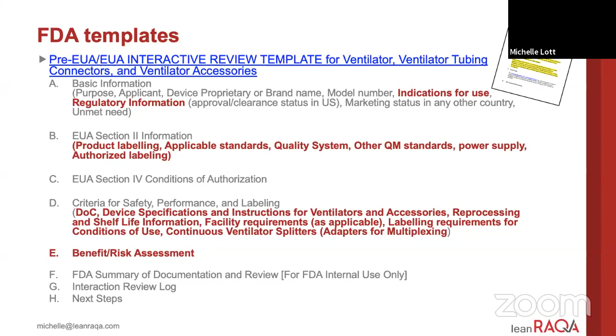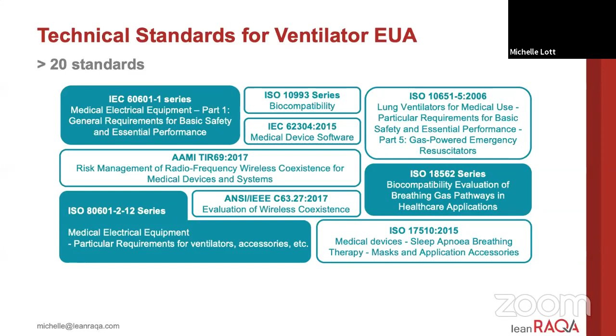So the FDA has a whole formal process for how to design and document design controls. And the most important thing is that risk management is integrated the entire way. And this even extends to the emergency use authorization. If you look at the table of contents for the emergency use authorization, several of the elements, which I've highlighted here in red, are direct outputs of the design and development and risk management process. So you really can't cut these corners. And in the ventilator EUA, there are over 20 technical standards from a variety of families that are cross-cutting and touch almost every aspect of your product design.